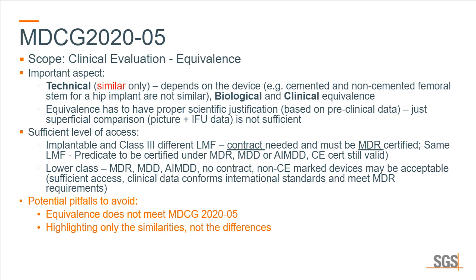Equivalence has to have proper scientific justification based on preclinical data. Just a superficial comparison is not sufficient. We have seen in the past many cases where in the clinical evaluation report, there was a comparison table of the manufacturer's device, which was in the scope of the clinical evaluation, and some competitors' devices or the manufacturer's own previous generation products. But the equivalence was supported by just a very superficial set of criteria. There was a picture that it kind of looks the same, and some cherry-picked performance parameters that showed that a number of features and parameters are equivalent.